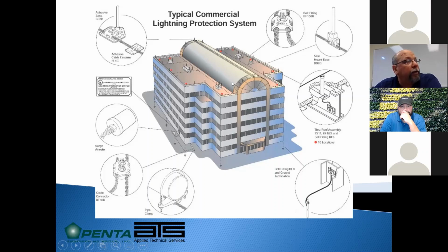And if it's a steel frame building, the rooftop system can be connected just under the roof level to the structural steel. Use the structural steel to carry the energy down to the ground, where we have another connection that takes it out to a ground rod. Or this can be a physical cable that's either run in a concrete column or somewhere along the perimeter edges of the building. And then at the base of the building, we'll go out to a ground rod or a ground ring. This is a down conductor. This is a through-roof assembly that in this case takes it to structural steel. If it is a concrete frame building, the cable would just go all the way to the ground.